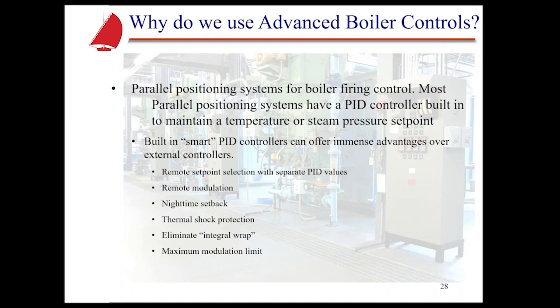Also, with the built-in PID controller, and most have this, or load control, this can give us immense advantages over external controls because it's part of that system. And one of the things we can do there, obviously, is remote set point selection with separate PID values. So that's built into many of these parallel positioning systems. Remote modulation, being able to select either local or remote modulation is a big deal. Then you could actually modulate that particular boiler or burner, if you will, from a building management system if they want to take control of that.